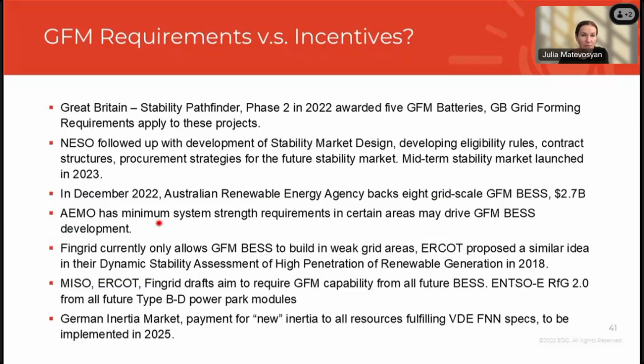And as I mentioned, AEMO specifications are voluntary at the moment. Fingrid currently only allows grid forming batteries to be built in weak grid areas. So this is a bit of an incentive. And ERCOT looked at a similar idea in the dynamic stability assessment study in 2018. But actually, currently ERCOT, MISO and Fingrid are drafting requirements for all future batteries to be grid forming. So this will be a requirement once it is approved.